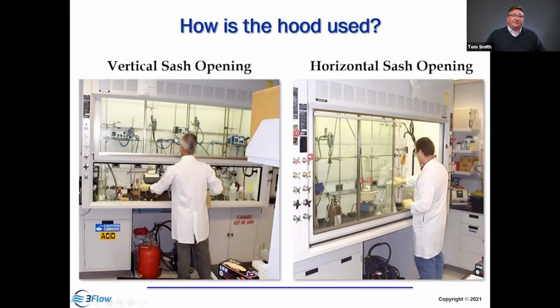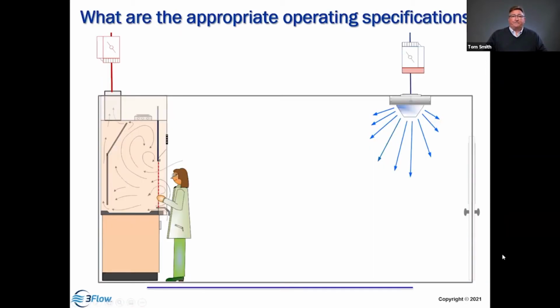But it makes it difficult to access the top interior of the hood, whereas a horizontal sliding sash hood limits your side-to-side access but gives you the ability to access the top interior of the hood. So both of these have value, but they can be limiting as well. So the vertical sash allows left to right movement but limits your vertical, and the horizontal panels limit your left to right movement but access the vertical. So these two designs are going to require different types of tests to evaluate.